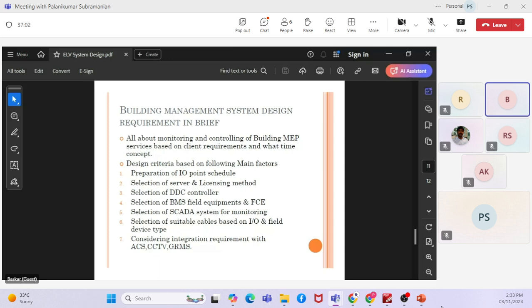Where the client and consultant are looking for monitoring only, we should not propose controlling as well, because the cost will increase. Again, the selection of the server licensing method differs based on the total IO points. We can have a software integration with the fire alarm system. There are different types of IO points. For example, the CRAC units we are integrating through Modbus. So this is a software integration, and there are hardwired points also. Hardwired means directly connecting a hardwired cable to the MEP units. Let's say for the booster pump, we are directly controlling and monitoring: we pull the hardwired cable directly from the BMS controller to the booster pump panel. That is one example.